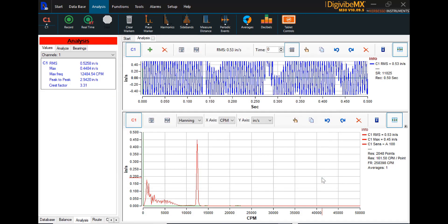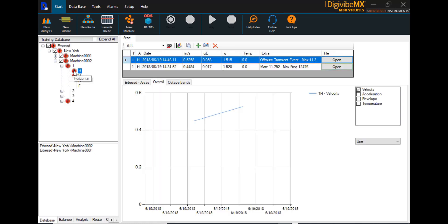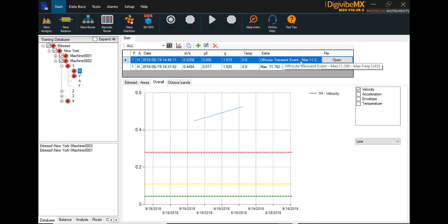And this off-route data collection has now been saved to machine 2.1 horizontal axis where we collected it. We can close this and close the analysis window, and if we go return to the database, open machine 2.1 horizontal, we can see the off-route transient event that we just collected as well as the last route data collection. So using these tools, you can create new machines, assemble them into routes for route data collection, you can save those routes and recall them later to be recollected, and at any time using new analysis you can simply walk out to a machine, take a data collection and save it to that machine wherever it exists in your database.